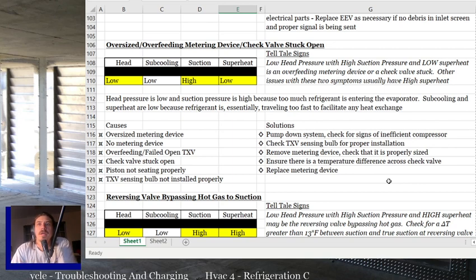If you've got no metering device in there, and this actually happened to me not that long ago, so it happens, right? You've got no metering device in there at all, or the metering device is too big. You've got a 5-ton TXV on a 2-ton system, or a giant piston on a smaller system, or the TXV's stuck open. Some systems have a check valve around the fixed orifice or the TXV. If it's a cap tube, they'll have a check valve around it. That check valve might be stuck open, so it's not metering.